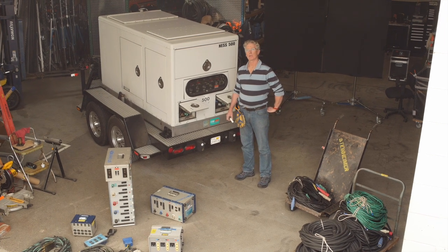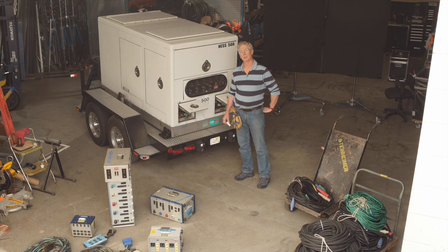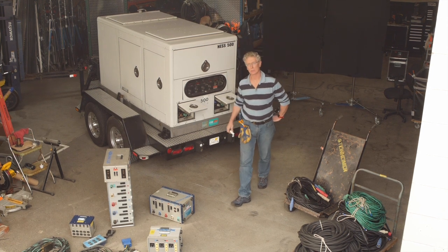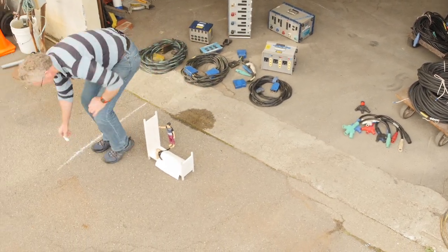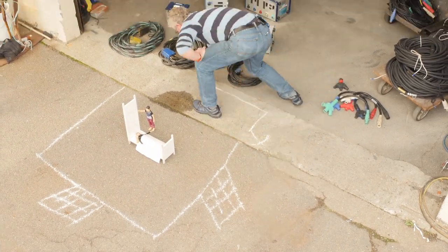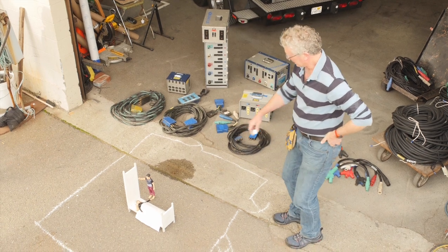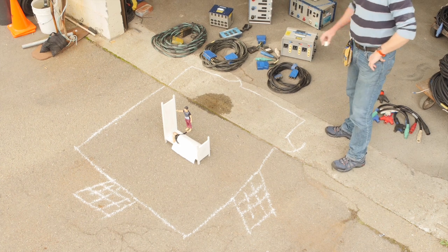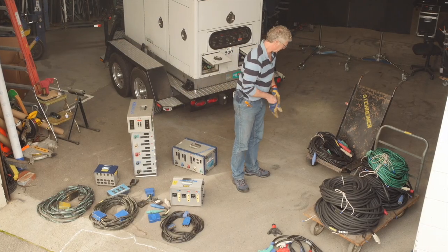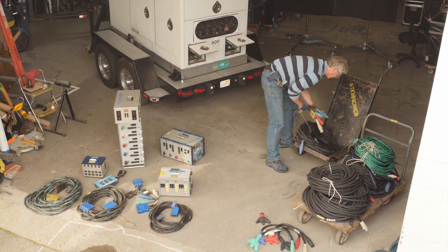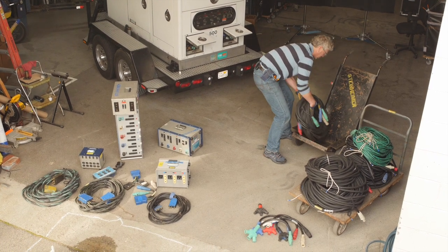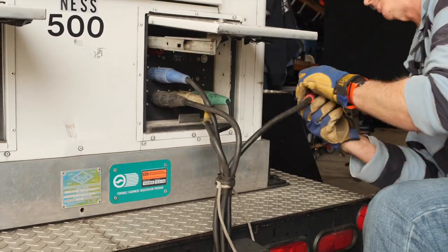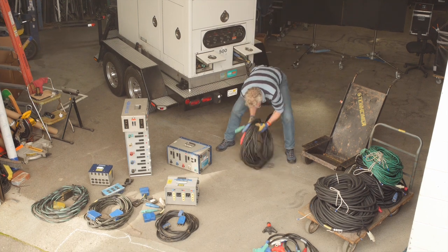Now we're going to start doing a little layout, but we've got a limited budget here so it'll be a pretty small set. We're going to start with a 500-amp generator set up for three phase. Our limited budget casting director cast Barbie and Ken, so here's our room — two windows, two doorways — and now I'm going to run some distribution. First, I'm going to grab some five-wire banded. I look at which end is the male end — the male end always goes towards power. I do the ground first, then the neutral, and then the order on the rest of the power doesn't really matter. It's not a bad idea to do a little strain relief if you can, and then walk the banded out.